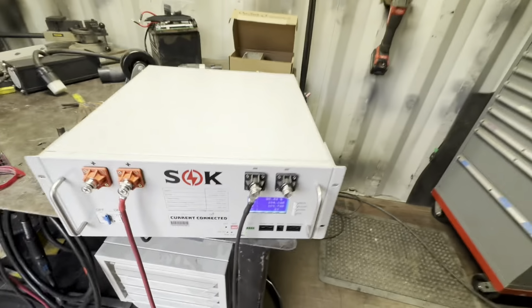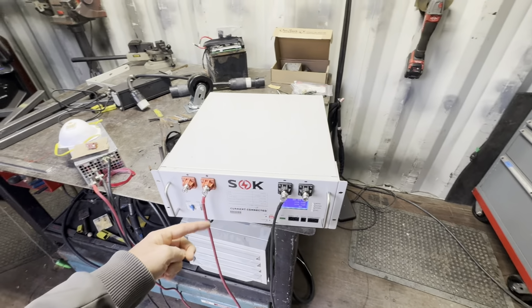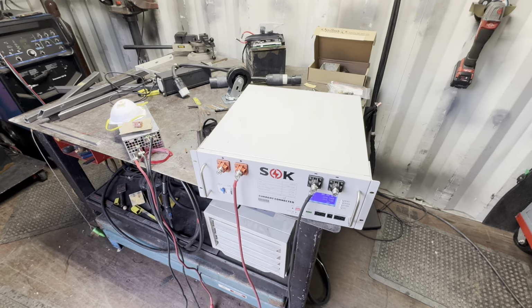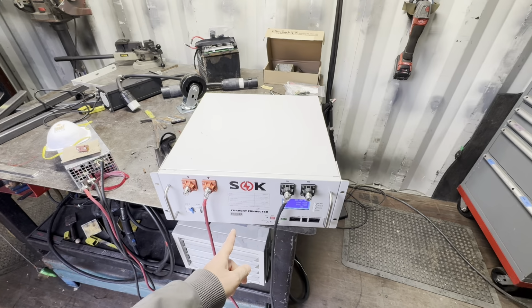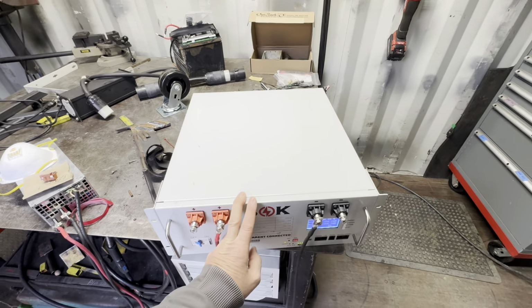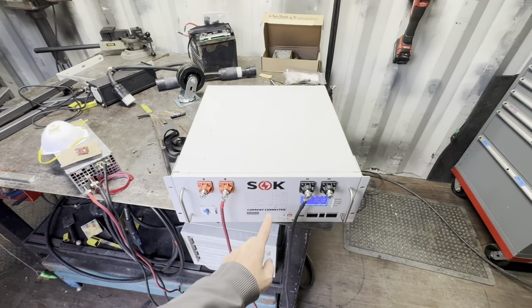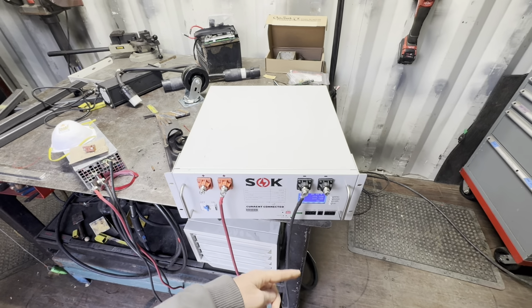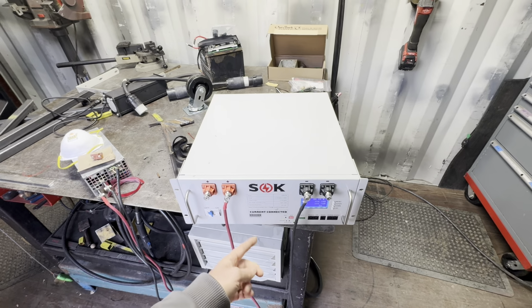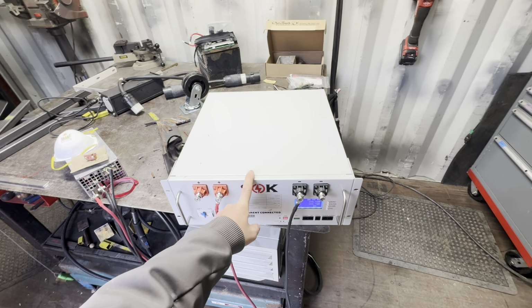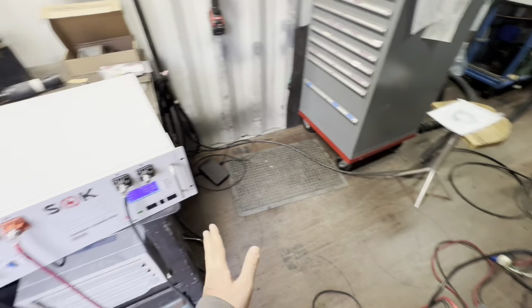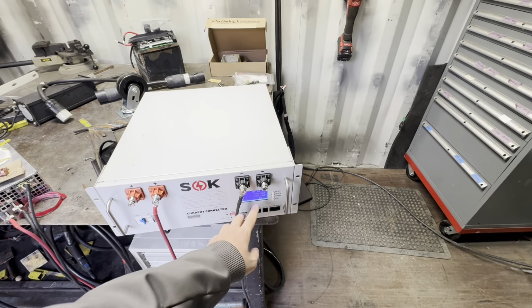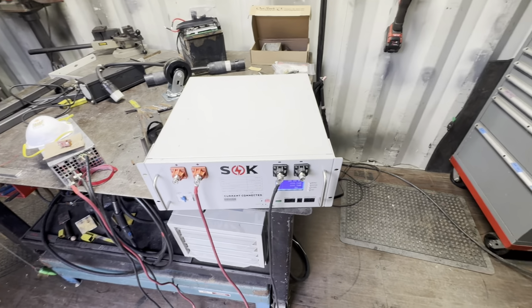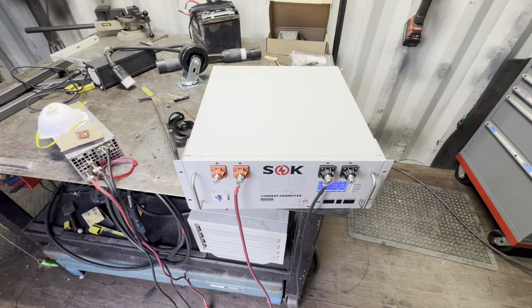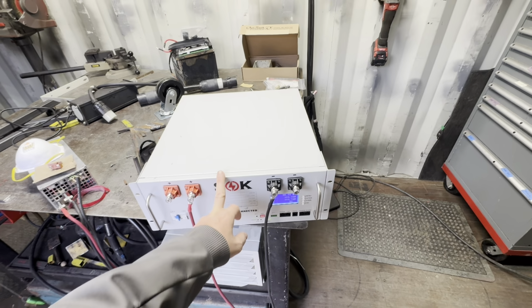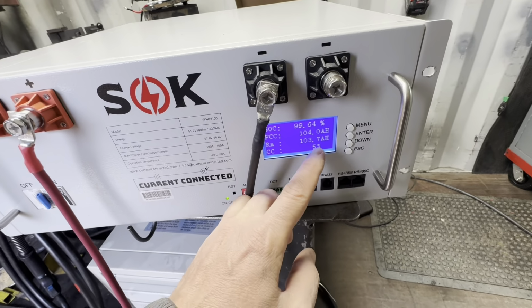So what happened is it went down to low voltage disconnect, and as the charger charged it overnight, the BMS inside monitored how much energy passed through it, and then it shut off for high voltage disconnect, or the charger shut off — I don't know which way it is, but maybe the charger shut off because it's actually saying 99.64 instead of 100. But I think if I got it up the rest of the way, it might actually be 104.